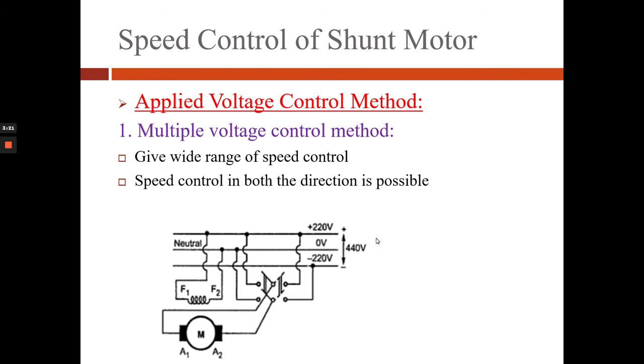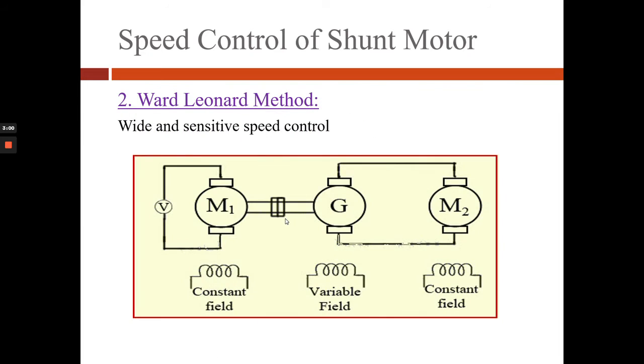Now we will see the applied voltage control method. In this method for a DC shunt motor, the field winding is connected to a constant DC voltage, but the armature is supplied with different voltages with the help of suitable switchgear as shown. This gives a wide range of speed control and speed control in both directions is possible.